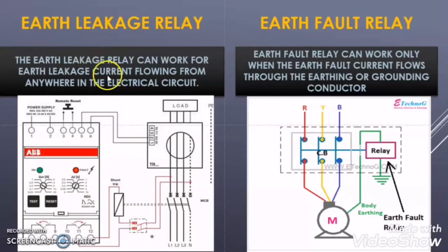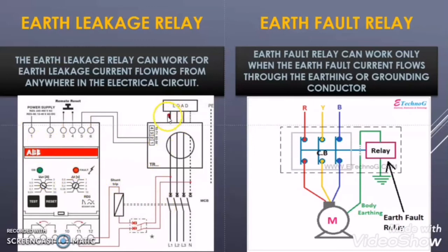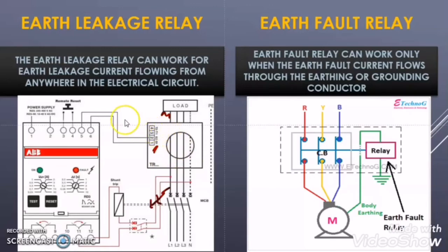The next difference concerns coverage zone. In the earth leakage relay, wherever the fault happens, it will trip. If a fault happens at the load side, the imbalance current is detected by the CBCT and it trips the circuit breaker. Even if the fault happens before the CBCT near the source side, the leakage current still creates an imbalance that the CBCT senses, and the earth leakage relay trips the circuit. So wherever the fault happens, the earth leakage relay always operates.